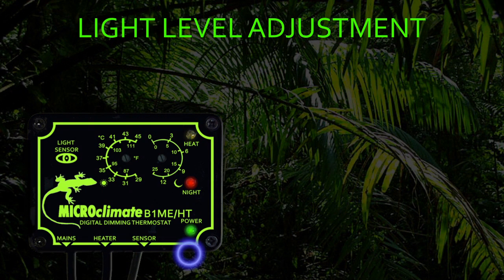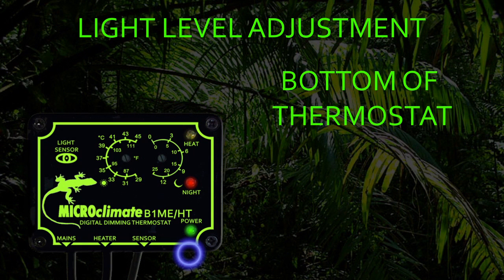The light level adjuster is located on the bottom of the thermostat next to where the sensor is fitted to the thermostat. The light level adjuster comes factory set at midway in its adjustment range. To fine-tune the light level that is required to switch the thermostat into night mode, the light level adjuster can be turned either clockwise to require it to get darker before switching into night mode, or anti-clockwise to require the thermostat to switch into night mode sooner.